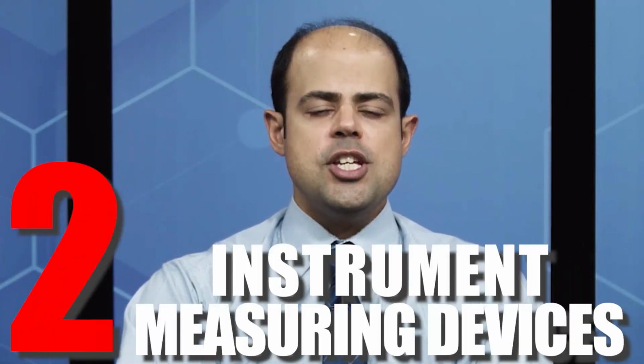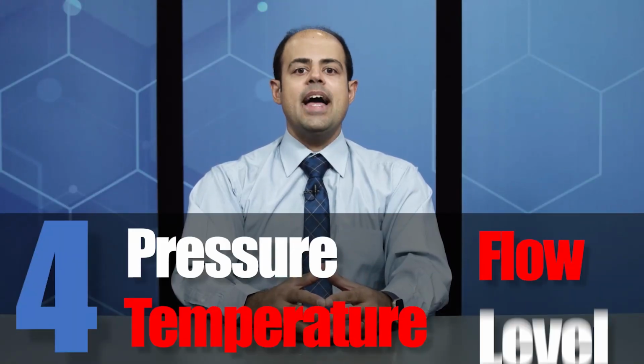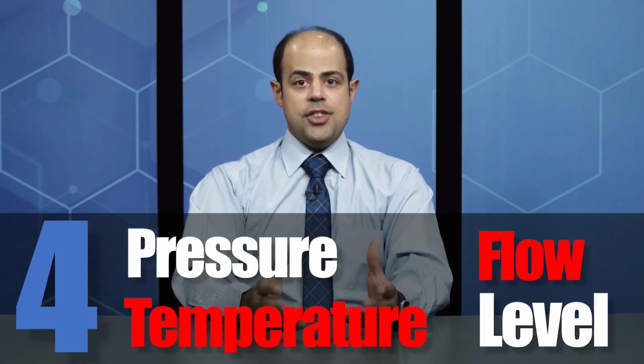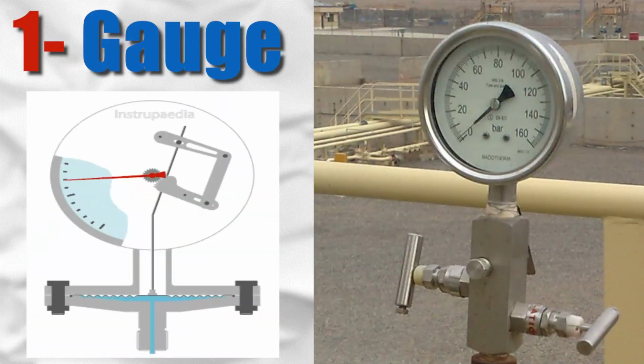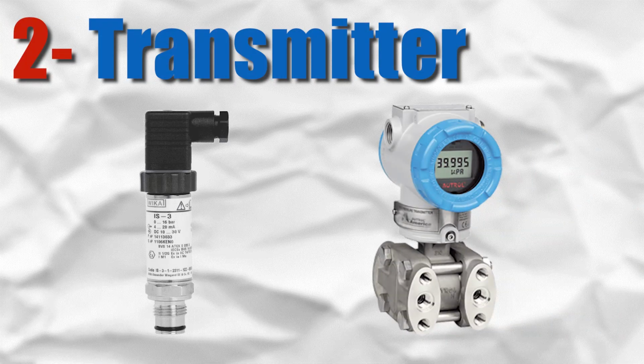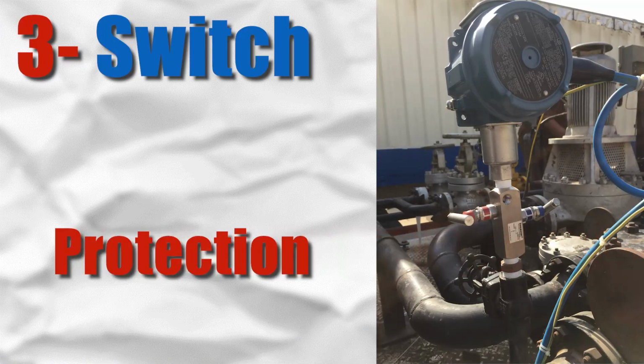This part is instrument measuring devices. Four quantities, which are pressure, temperature, flow, and level, are considered in this section. There are three types of instrumentation which play important roles. The gauges measure the amount mechanically. Not only do the transmitters measure the amount, but they also send it as a signal to the control room to indicate it on a computer or display. And the last one is switches, used for protection.